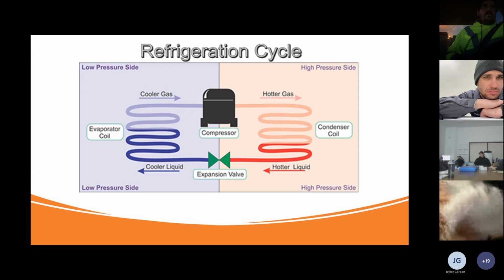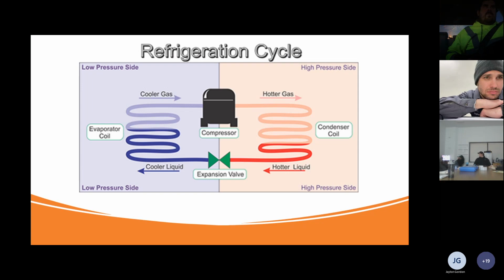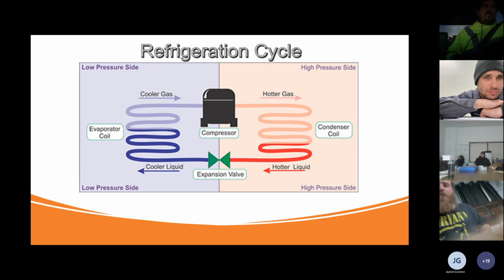Yeah. So it goes into knowing the state of the refrigerant, too. Like Dustin was talking about the state of it, when it comes out of the compressor, it's high pressure, high temperature. It goes through the condenser. It changes from a high temperature, high pressure gas to a high temperature, high pressure liquid, and so on. So that's another thing you need to know: what state it should be in, and what temperature or pressure it should be at, at what point in your refrigeration circuit. What are you saying, Travis?